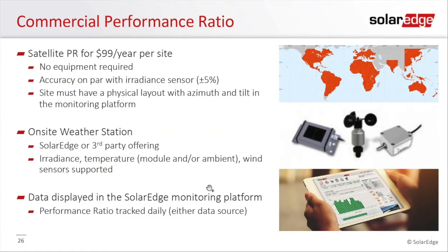One of the other offerings that we've just released to the market in the last 6 months or so is something else that could help with cost savings on projects. And we're highlighting it here because I think it's particularly applicable to 208 applications. 208 applications tend to be smaller. You're not looking at multi-megawatt, you're looking at tens of kilowatts, maybe 100 kilowatts, a couple hundred kilowatts. And the cost of a full weather station, for temperature, irradiance, and even wind, is fairly high.